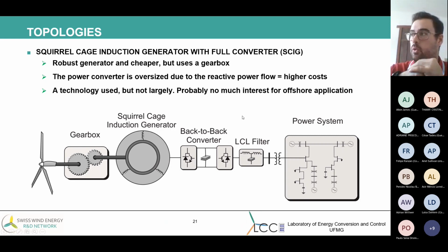The squirrel cage induction generator with full converter, known as the SCIG, is similar to the fixed speed technologies. We use the squirrel cage induction generator, so we have a gearbox, but instead of connecting the generator directly to the grid, we have a power converter, in such a way that the power converter can guarantee the variable speed of the system at high efficiency. The advantage is the robust and cheaper generator. The generator is very efficient, it's cheaper, it's very robust, but it uses a gearbox. The gearbox has the problems of maintenance.